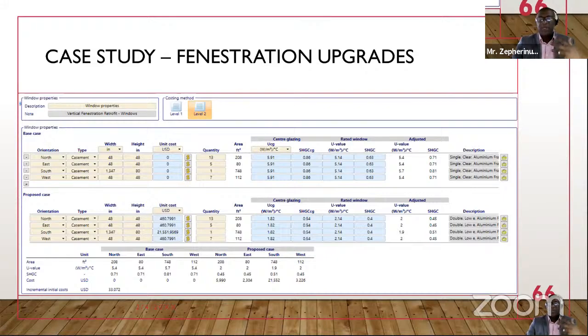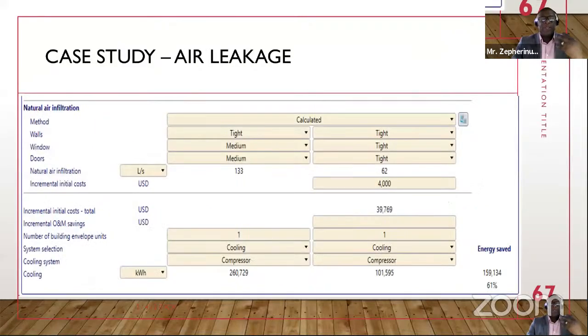So the RETScreen Expert was used for this case study. And what we saw is that, in addition to the fenestration upgrades, the leakage, the building was made tighter, so the envelope was made tighter, especially windows and doors. So move from medium to tight. So making the envelope tighter, upgrading the fenestration, resulted in a 61% energy savings, depending on the cooling loads.